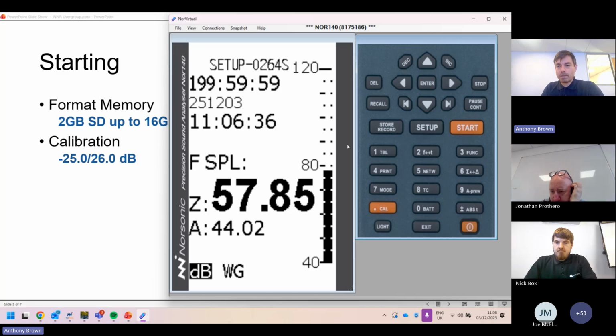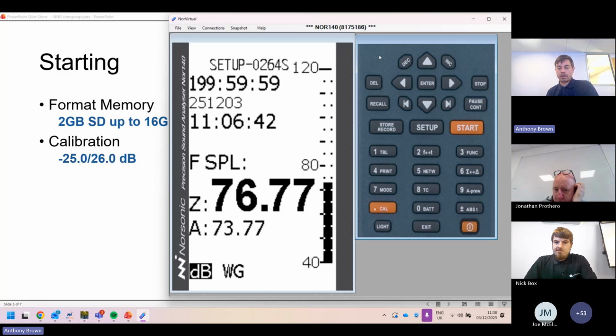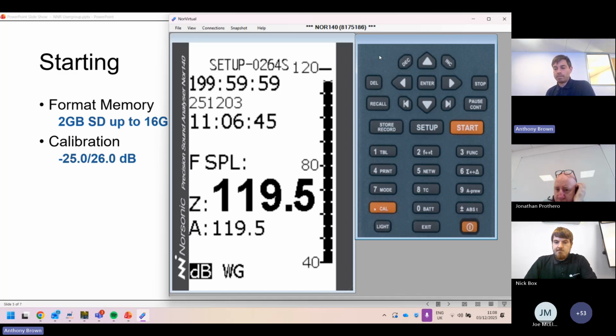Let's have a look at just the calibration. I just want to make sure that everybody was okay with the calibration. So I'm just going to place my calibrator on the end of the meter. So at the end of my measurement, I'm going to calibrate the meter by placing the calibrator on the end of the meter. I'm going to make sure it reads 114. And if it doesn't, then we would just press the CAL button on the screen.